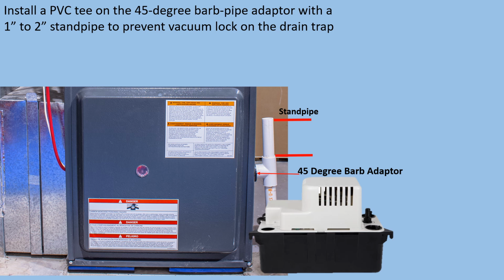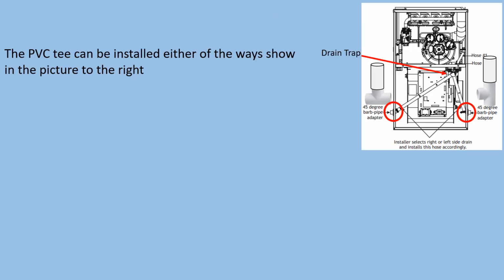Install a PVC T on the 45-degree barb adapter with a 1-inch to 2-inch standpipe to prevent vacuum lock on the drain trap. The PVC T can be installed either of the ways shown in the picture to the right. You can stick the end over the 45-degree barb adapter and put your standpipe on like the left side, or you can do it like the one on the right. Just put it on there, the standpipe goes up, and you're going to drop right into your condensate pump.